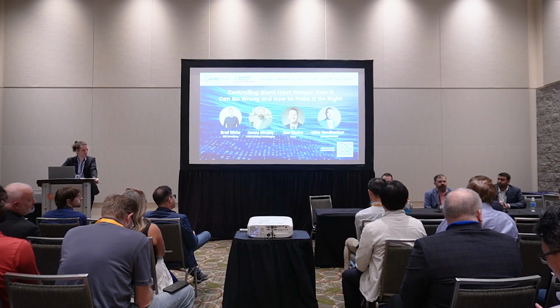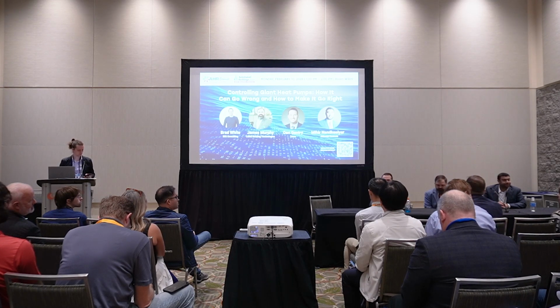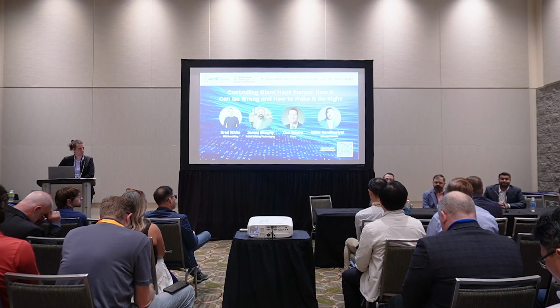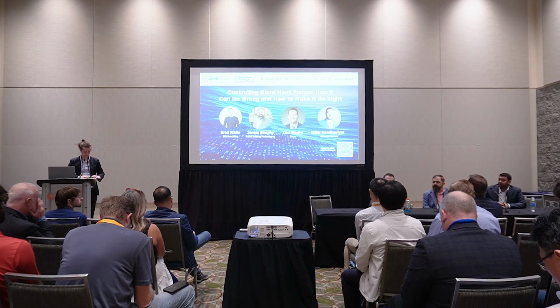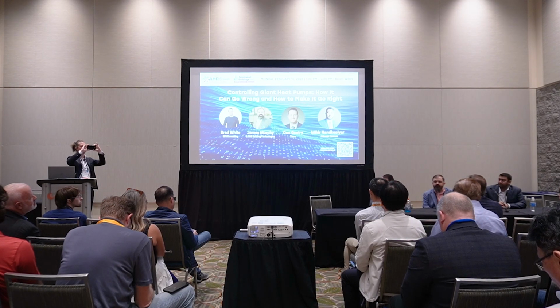heating or electrification. A lot of it's new designs, new construction, so working with consulting engineers to lay out optimal designs, picking water temperatures, delta Ts, pumping configurations, talking about redundancy and what we do for cold climate heat pumps, getting some large heat pumps like heat recovery applications for high tech, like semiconductors and data centers, where we're talking about thousands of tons as opposed to hundreds of tons.